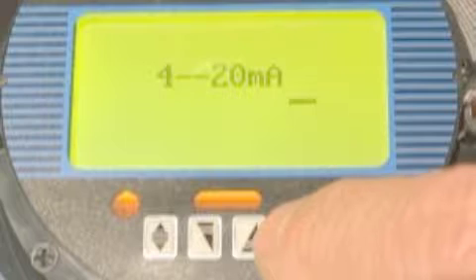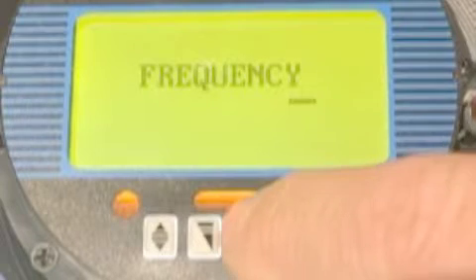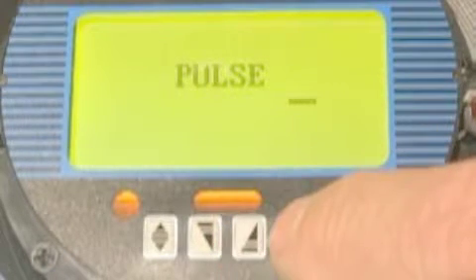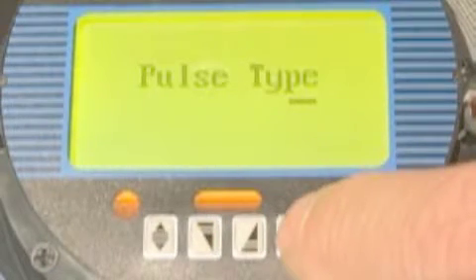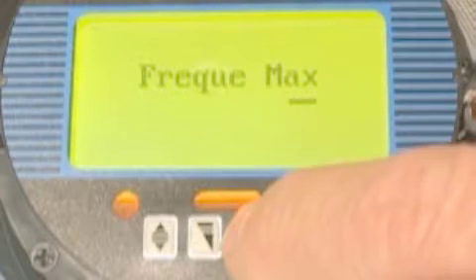We don't really care about this analog type. It's 4 to 20 milliamps, which is the standard. Pulse type. You can either have frequency or pulse. Now I'm pressing the right button. Pulse type. It can be the max frequency, 5,000. And so these other variables.